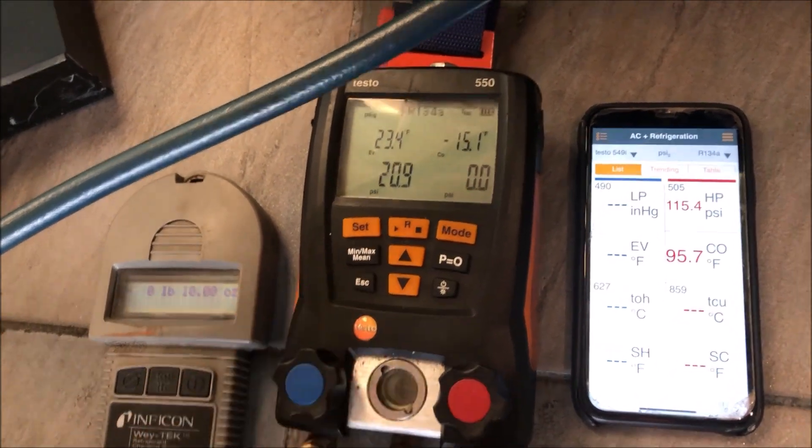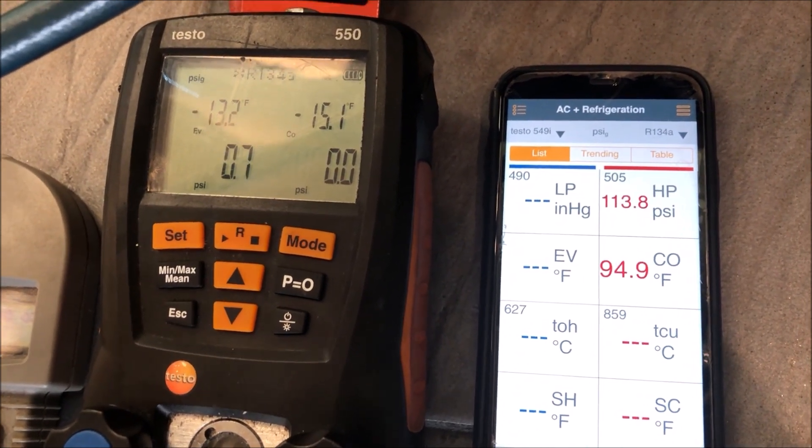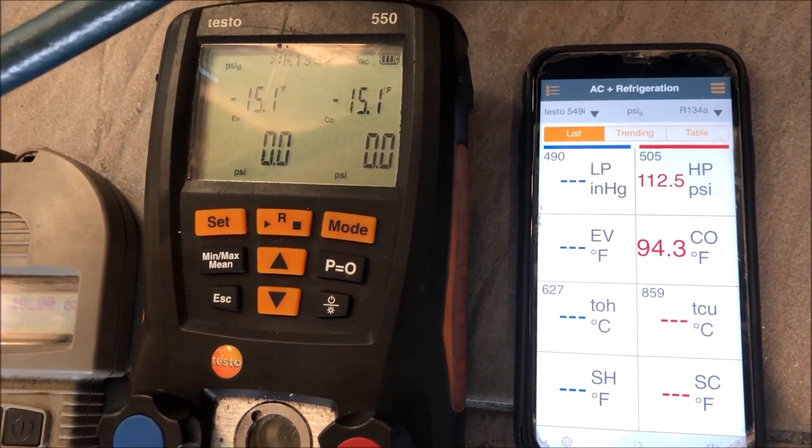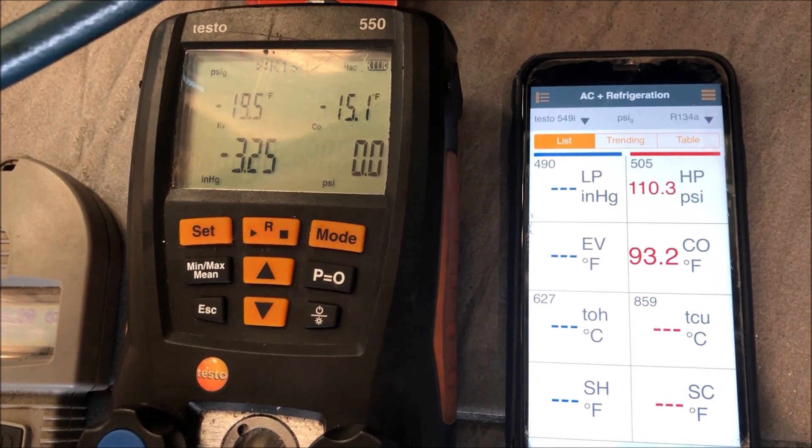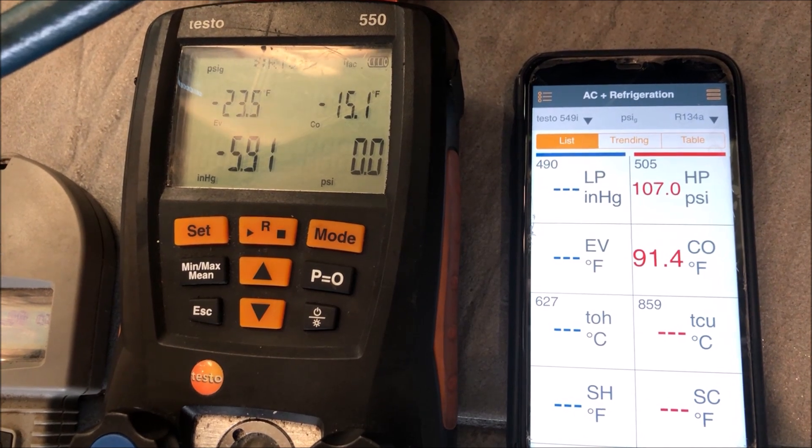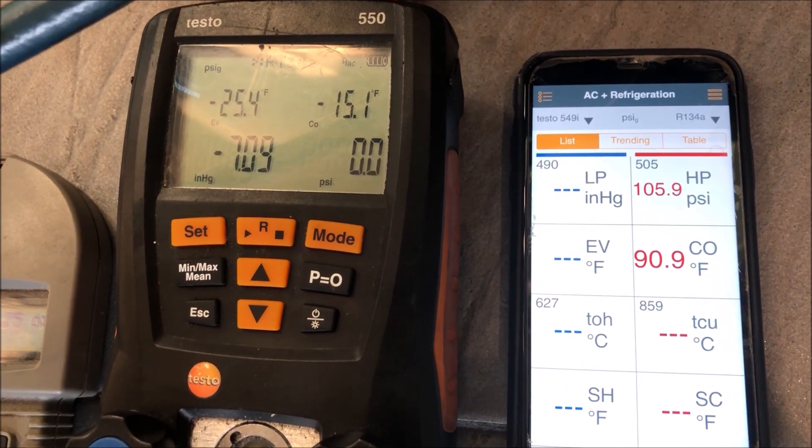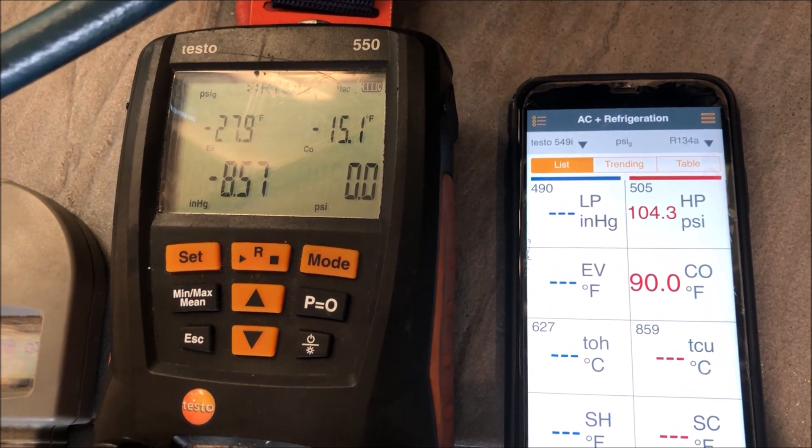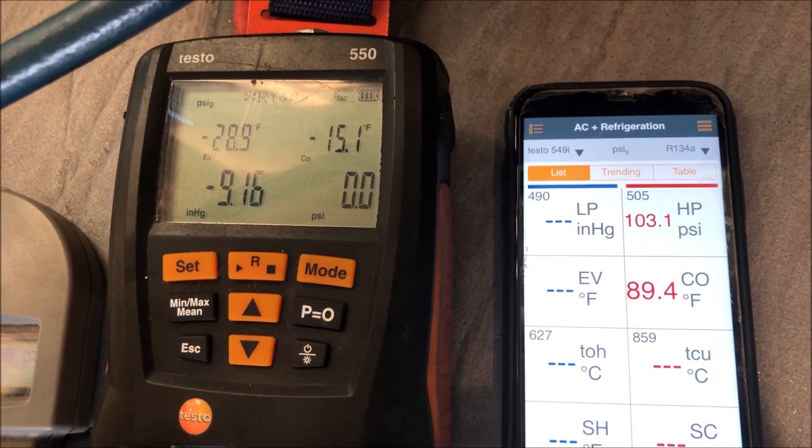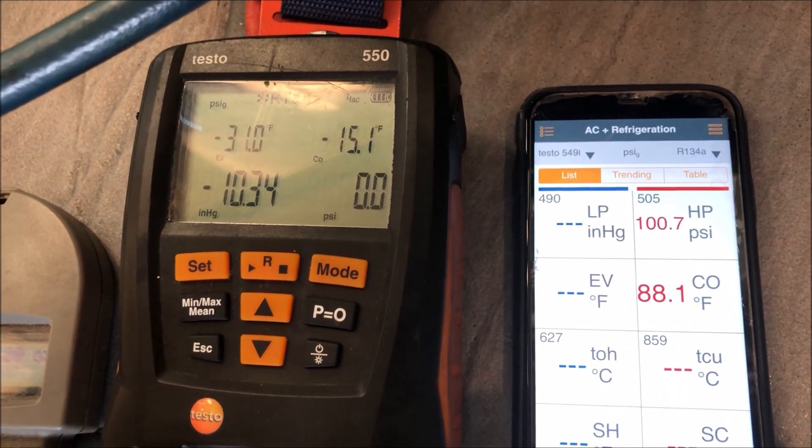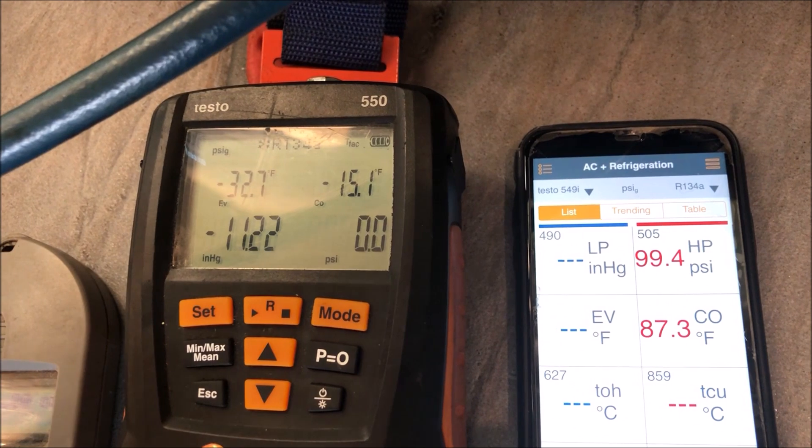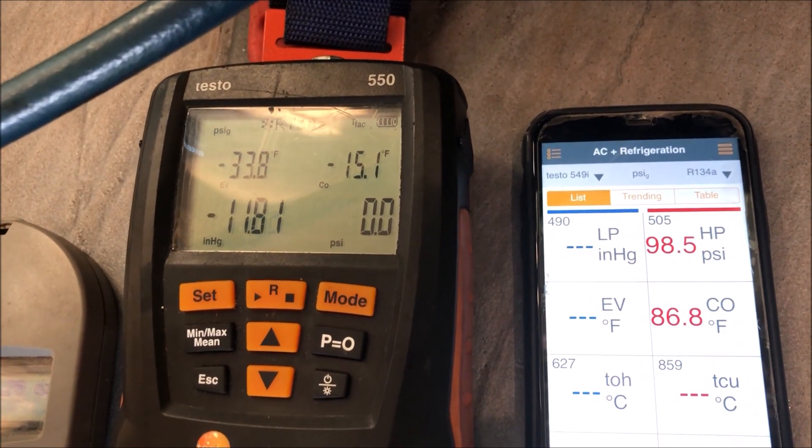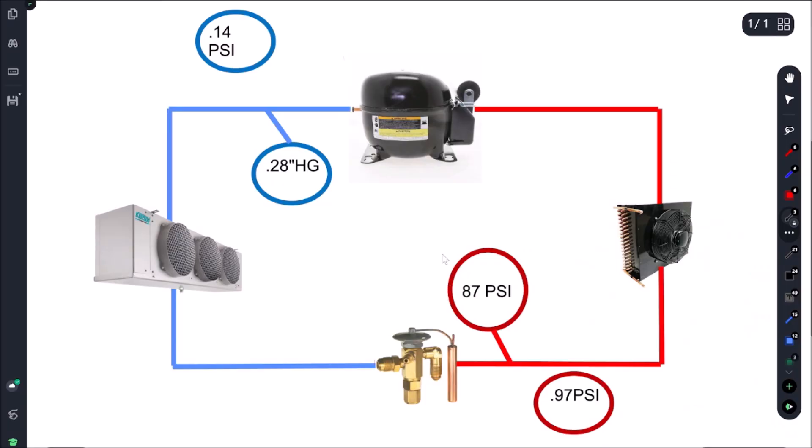All right, so let's go ahead and close off. I put in the full charge there, so we're definitely gonna be overcharged, but that's gonna tell us right away if we're restricted or not. And you can see we're pulling right into a vacuum. And watch our condenser saturation. It was at 92 Fahrenheit, watch it start dropping. We were looking for around 97, somewhere in and around there, and it's dropping back to the pressures we had earlier, which we were in a vacuum and 87 Fahrenheit condenser saturation. So that means we have a restriction in the system.